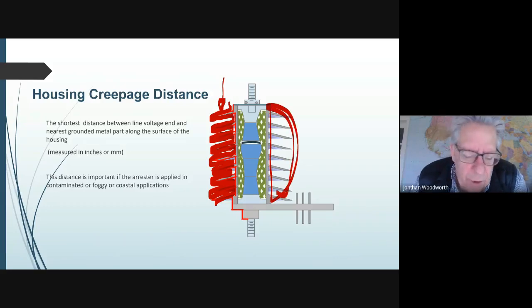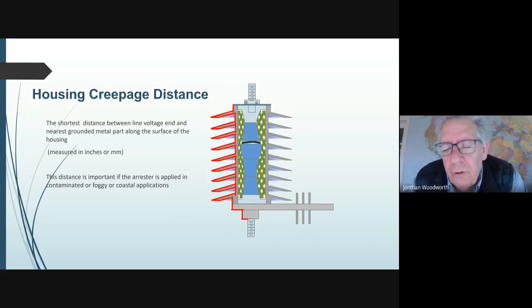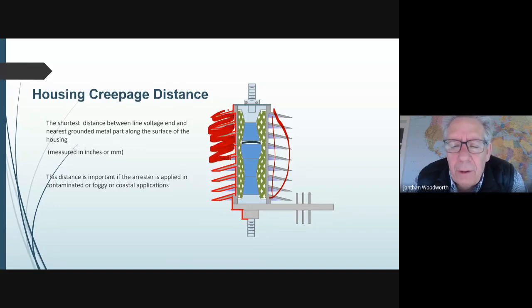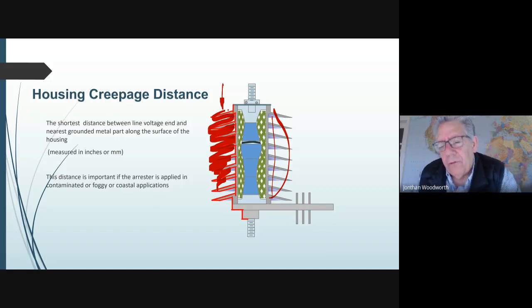So when an insulator or the insulation on the outside of an arrestor is very, very wet, or contaminated and wet, say contaminated by salt water, so a conductive contamination, it can flash over. If we didn't have the sheds, it would be a short distance and it would flash over. So we elongate the surface on the outside by putting these sheds on. So these are necessary for outside arrestors, but not necessary for inside arrestors. When I say inside arrestors, they are often used in an indoor substation or industrial substation or in a train station, that kind of thing. You don't need the sheds if they're protected from the weather.